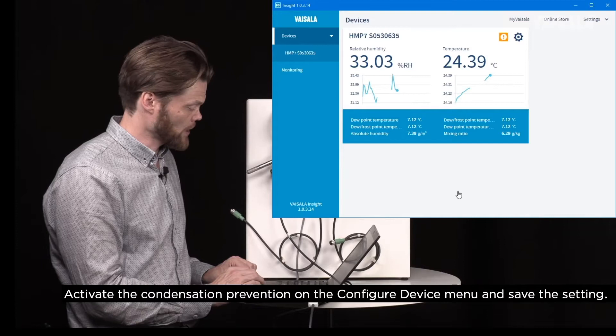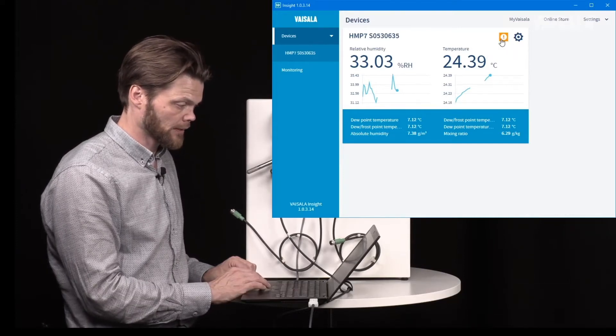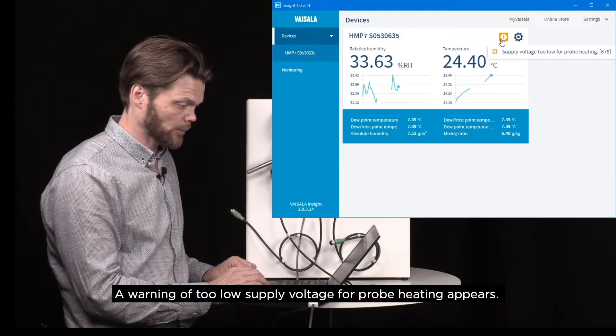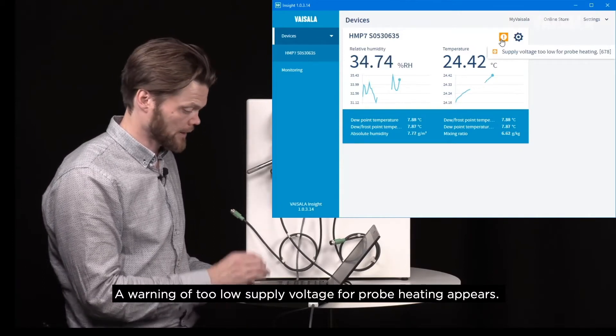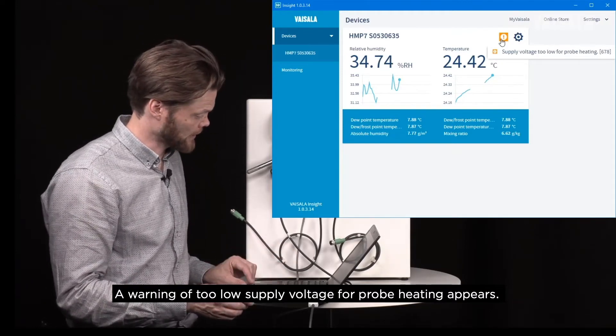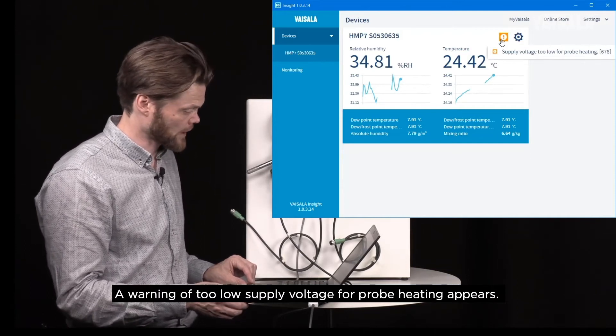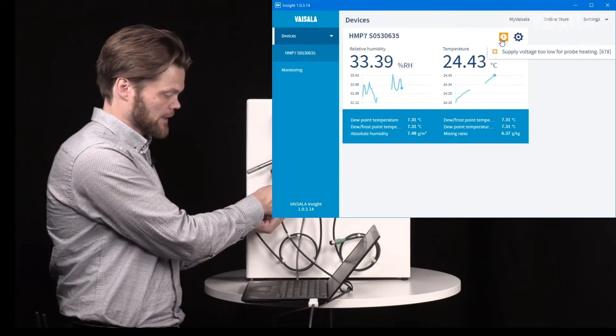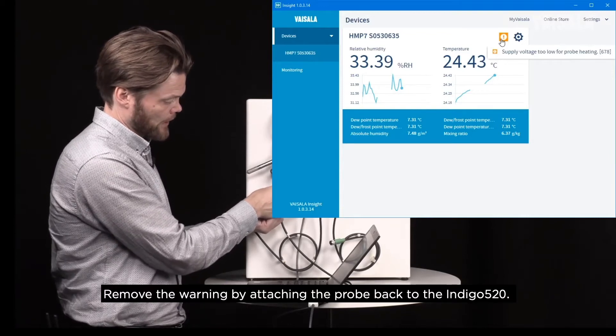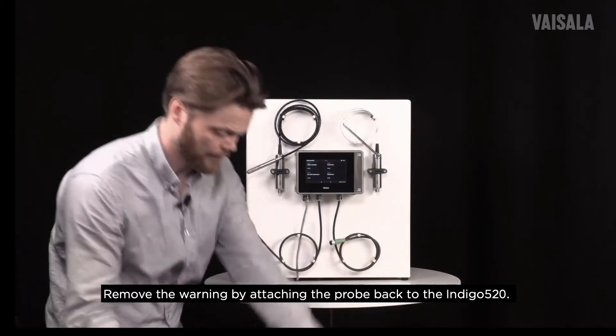It's worth mentioning that we will have a warning here telling us that the supply voltage is too low for probe heating. That's because we are using the USB cable, which is not able to provide enough voltage for this functionality. Let's fix that by putting the probe back into the Indigo520.